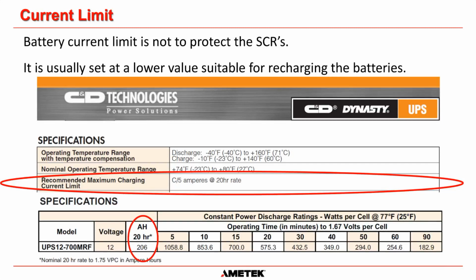For wet cell batteries, I have no idea why they have limitations on the battery. But that is why we now have two-stage current limit, because most of the battery manufacturers are now telling us that the current to the battery should be limited to a certain value.